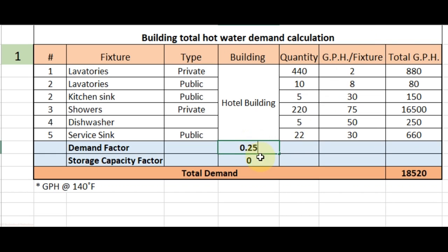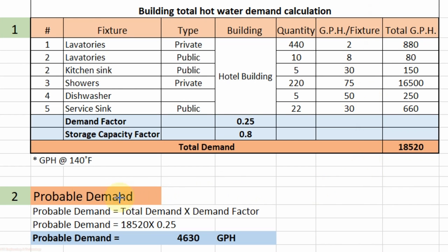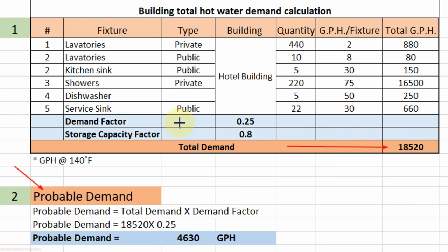The demand factor for the hotel building is 0.25 and the storage capacity factor is 0.80. Our next step is to calculate the probable demand. The formula is: probable demand equals total demand multiplied by demand factor. Total demand is 18,520 GPH and the demand factor is 0.25. When we multiply 18,520 by 0.25 we get 4,630 GPH. So our probable demand is 4,630 GPH.